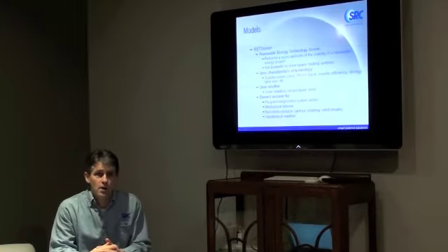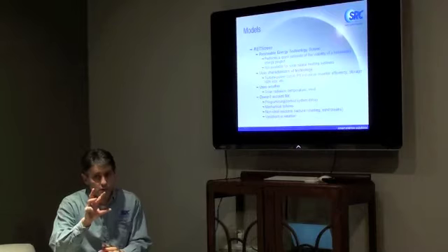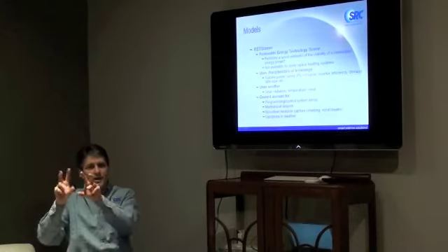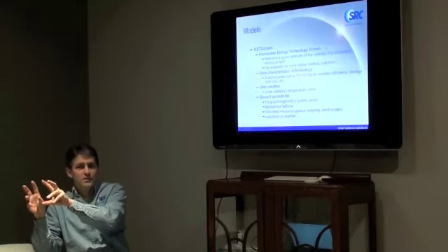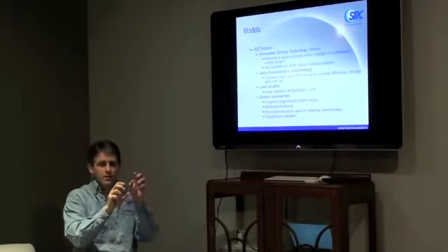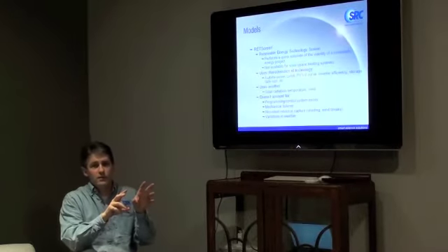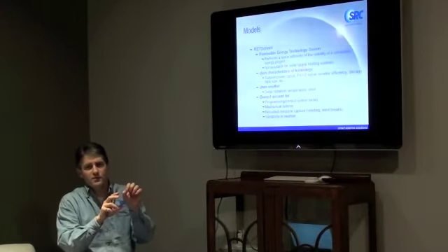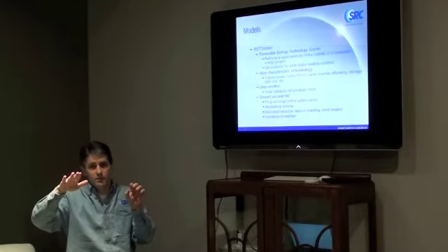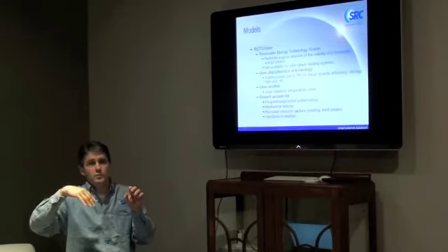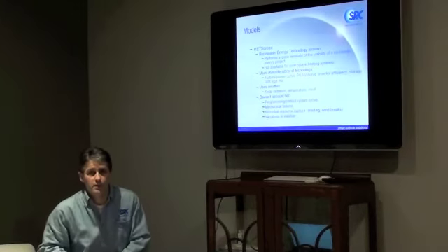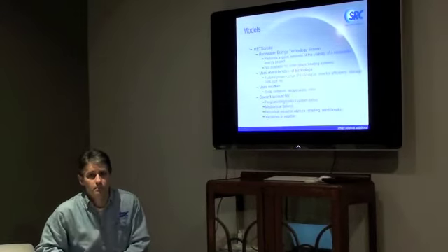There are factors you can adjust, that you can put in, but you have to be able to take that information that you know about the site and turn that into a factor that you can then put into RETScreen. But you only have one factor. So if it's shading, for example, the factor is going to be different in the summer than it is in the winter, which means you can't handle snow cover on PV panels or solar thermal panels. You can't do monthly factors.